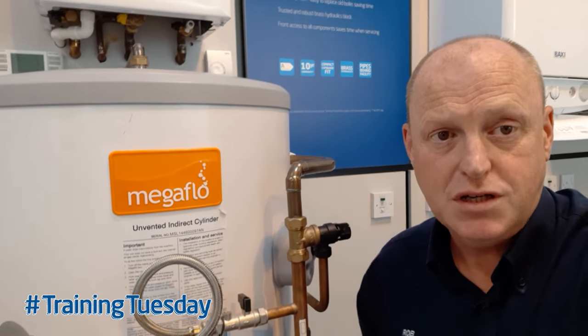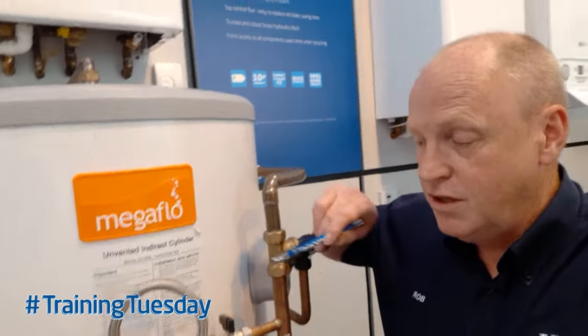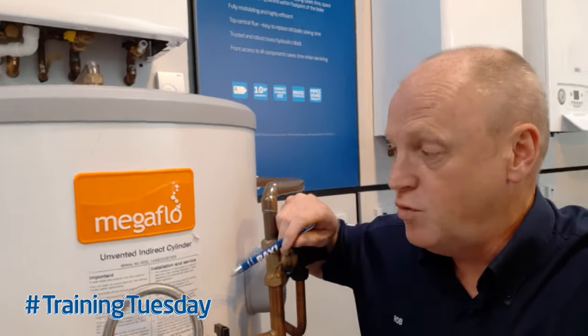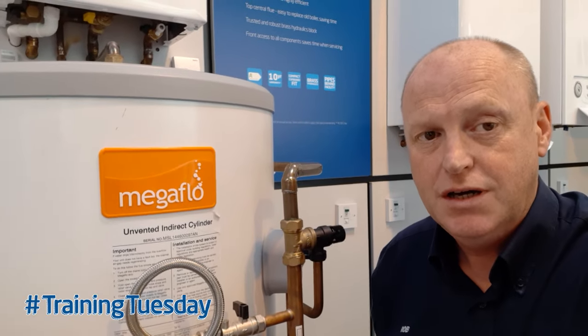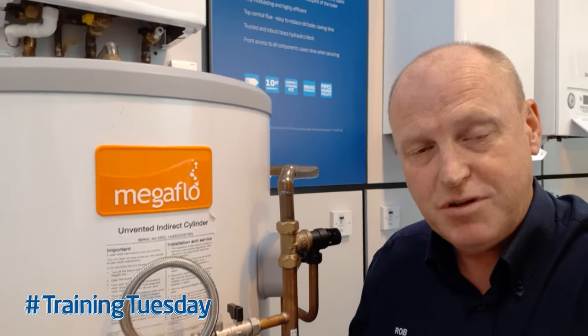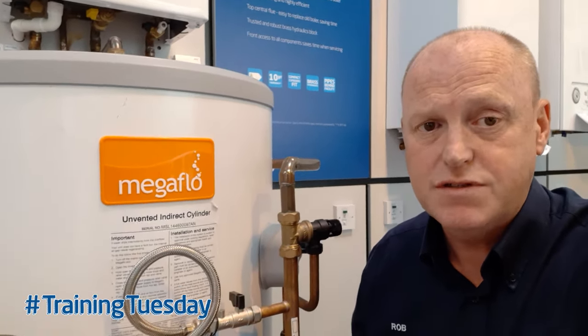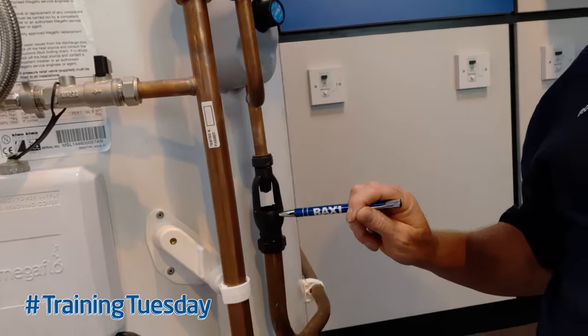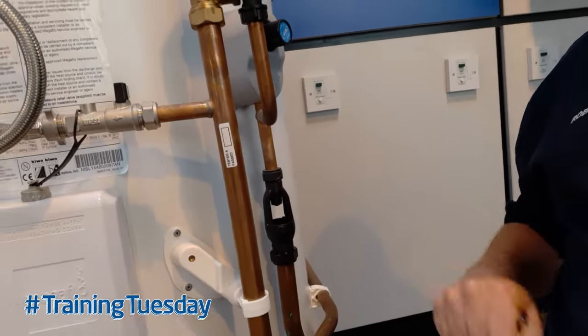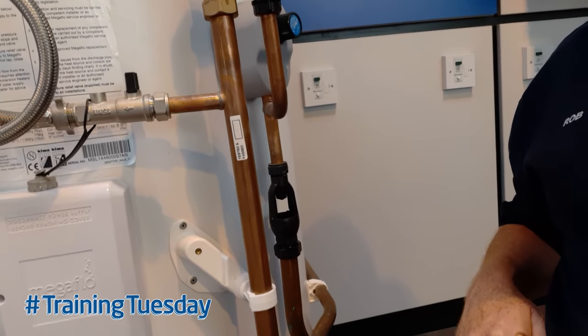The Megaflo cylinder has got an internal air bubble built into it to absorb any expansion as hot water is heated. A symptom that the air gap has been lost — because it dissipates over time — is that when we look at the tundish, what we get is a small drip from the tundish as the water is being heated.